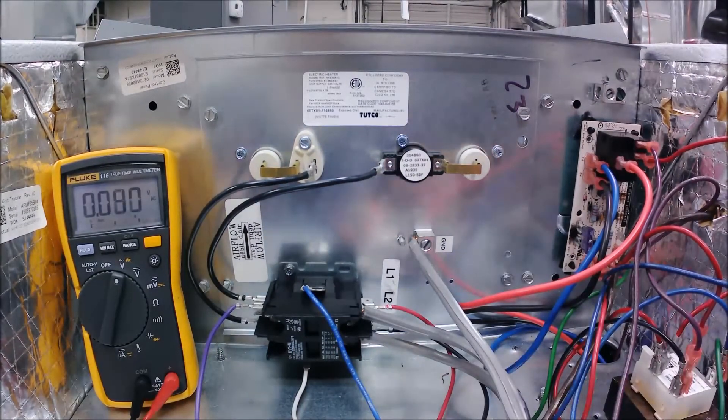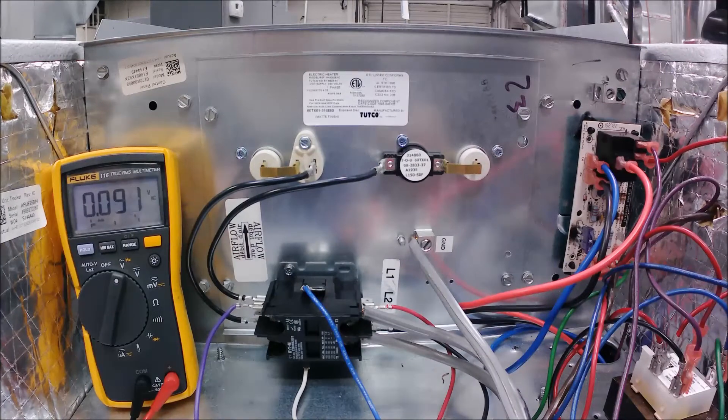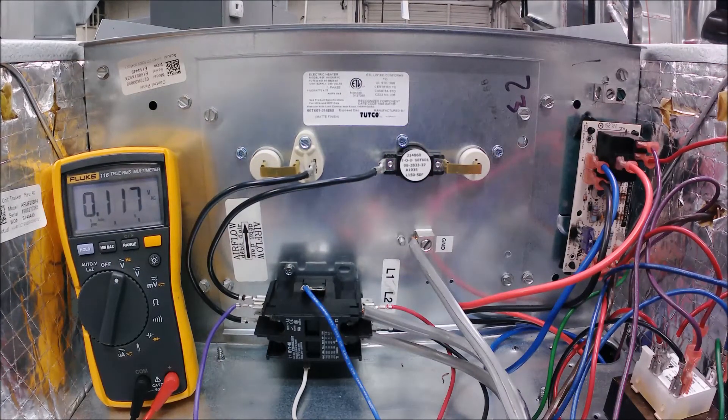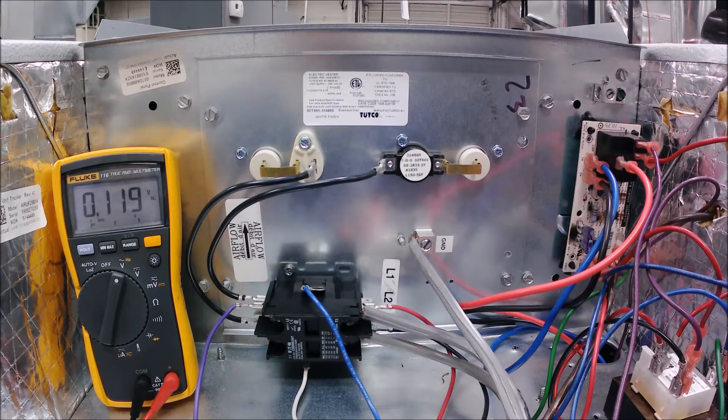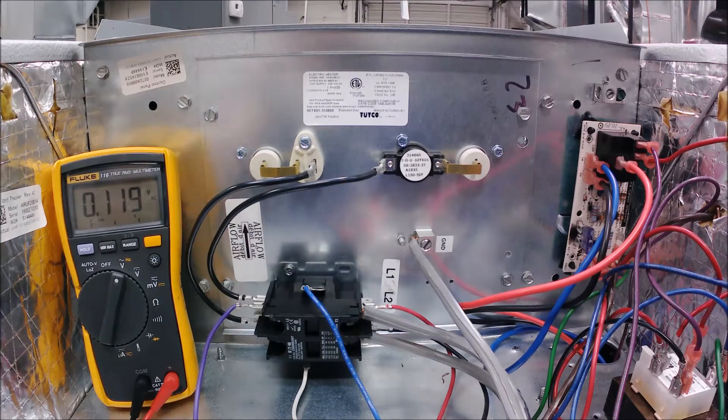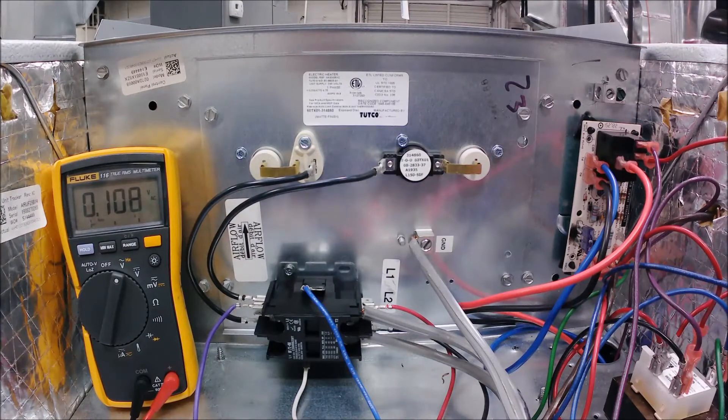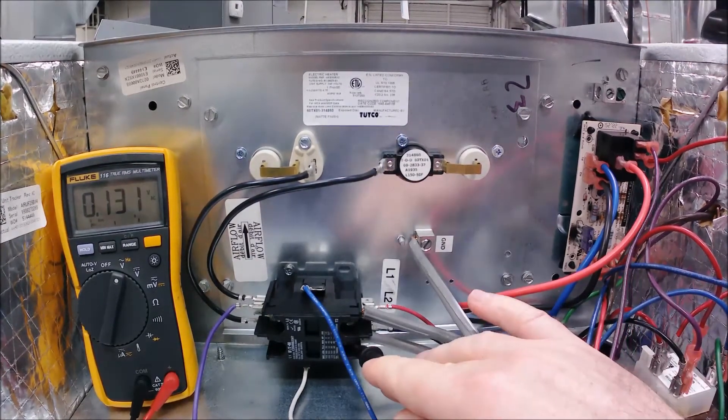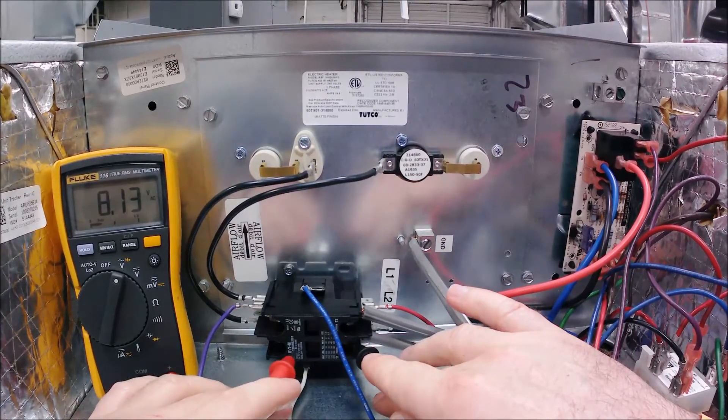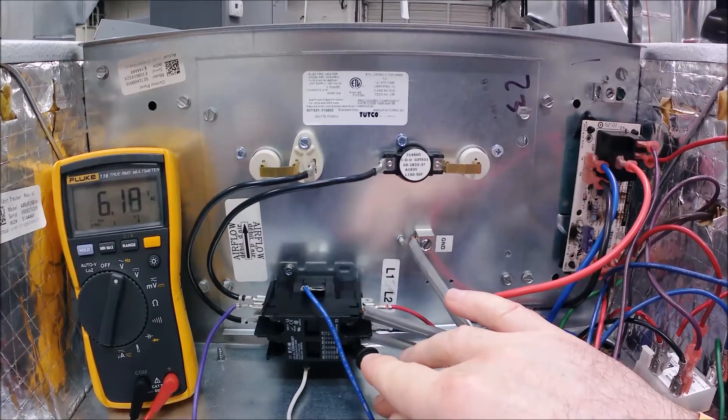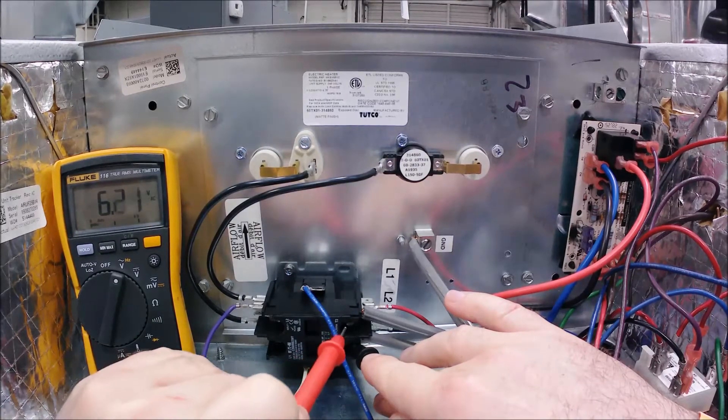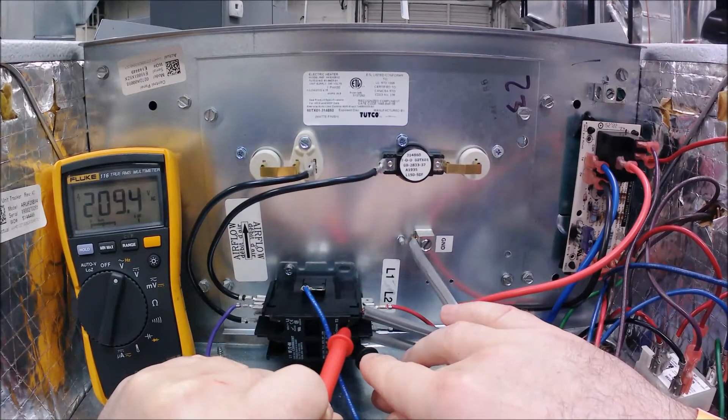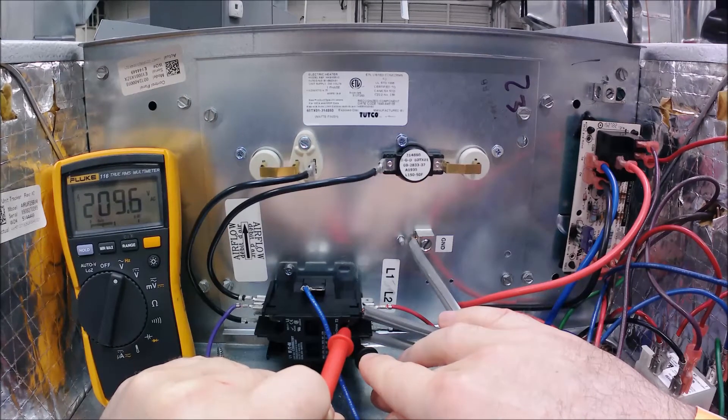So hopscotch troubleshooting is very simple. We're going to leave one lead stationary and we're going to move the other one. What I'm going to do is with my right hand, I'm going to come down here on the terminal labeled L2 - this is the underside of the contactor. Now I just did a voltage check here and you can see that I've got 209.6, 209.7, what have you.